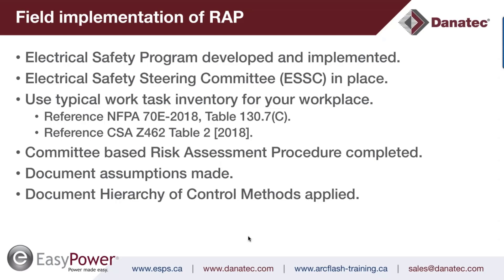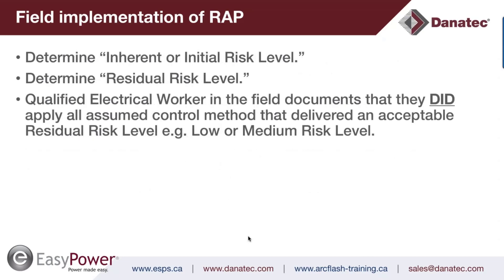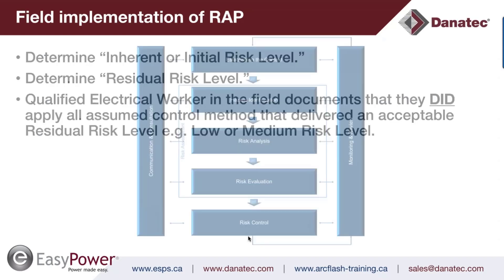Committee-based risk assessments would include a management sponsor, an electrical engineer if available, an electrical maintenance supervisor, and representatives of the electrical workers. The committee performs risk assessments for typical work tasks and delivers risk levels to the working community. Workers then confirm application and document their application of the hierarchy of control methods assumed by the committee. The process starts with an inherent or initial risk level, applies all hierarchy of controls simultaneously, and achieves a residual risk level. The qualified electrical worker shall document their application of the assumed control methods.